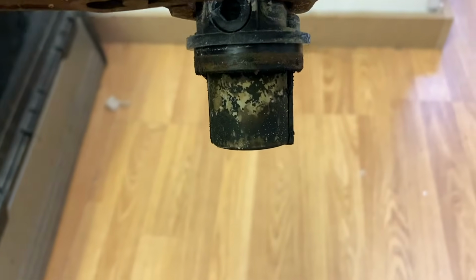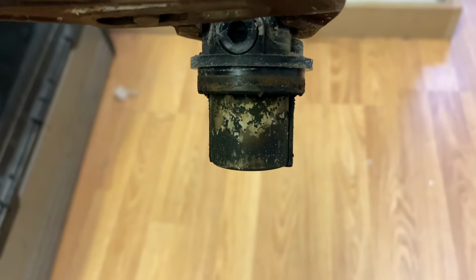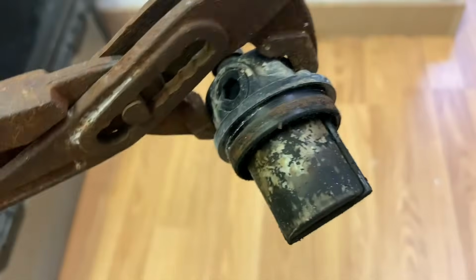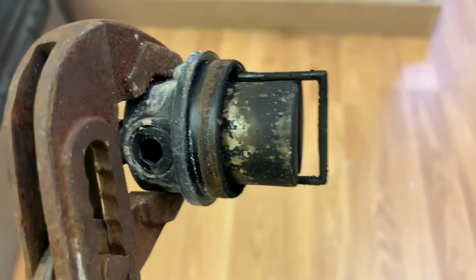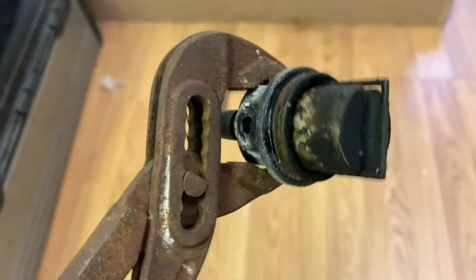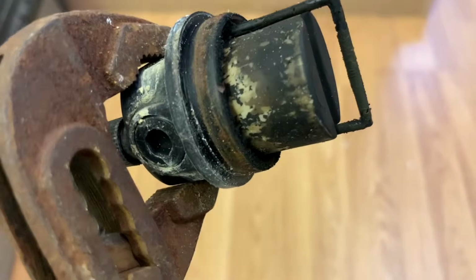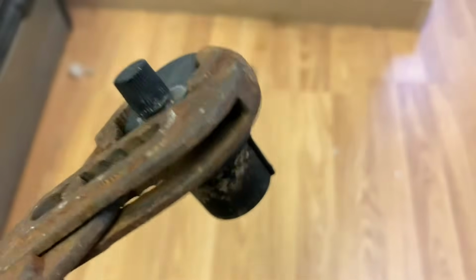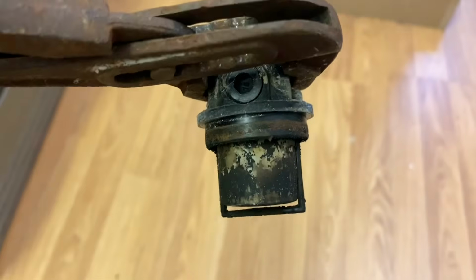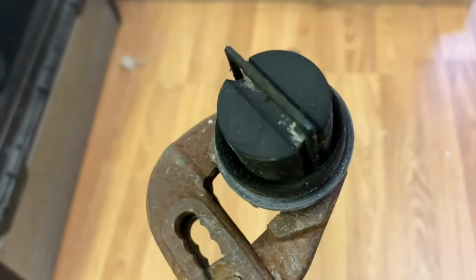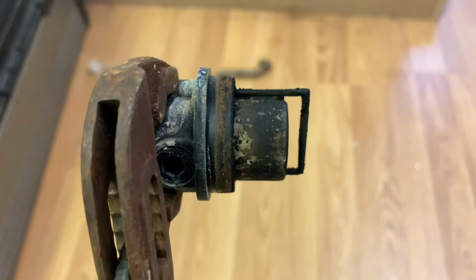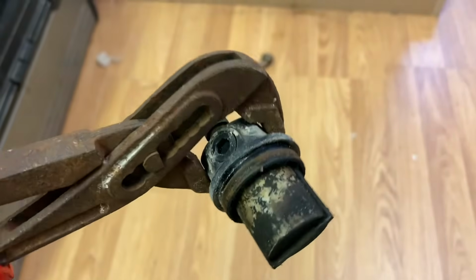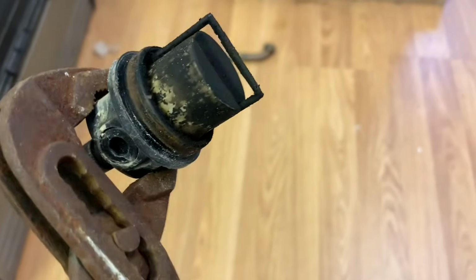So the way these work, dead straightforward, is when it's down like that, that means it's completely full of air, and when the slide goes up, the water pushes it up there and pushes the valve off. So that means there's air coming out the bleed at the top, and when it's up to the top like that, that means it's full of water. Now you can see how crusty it is. This is the biggest problem we have as heating engineers, is repairing boilers on dirty systems. So guys, make sure you always flush and clean your systems, or this is what happens to automatic air vents. Let's get this back in and let's have a look at some other parts.